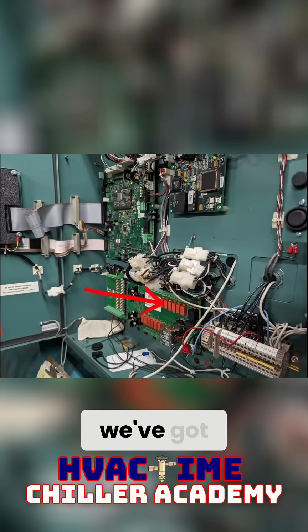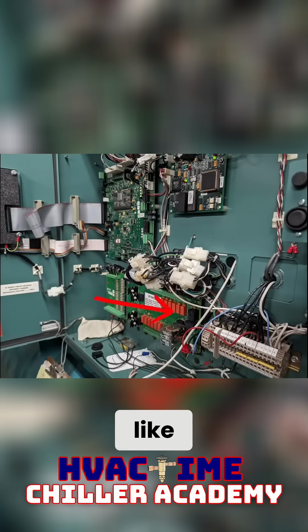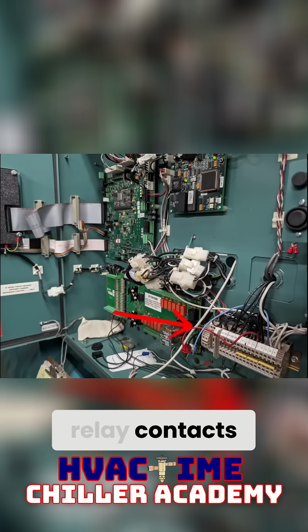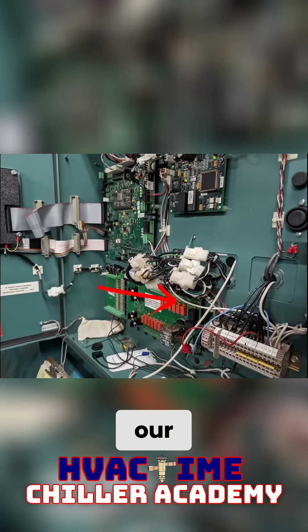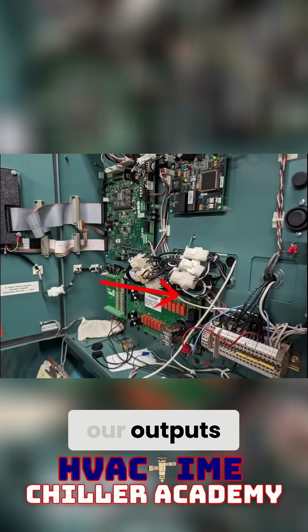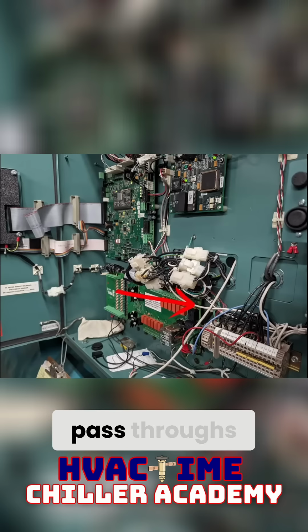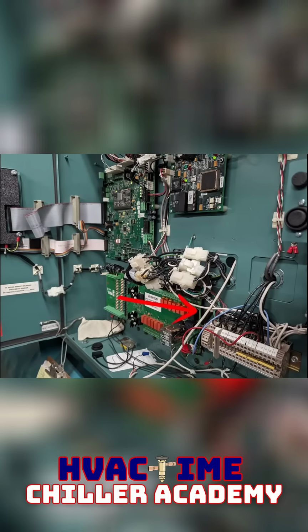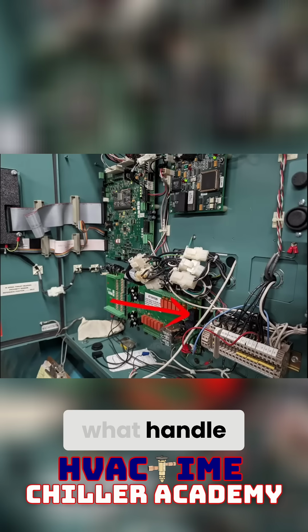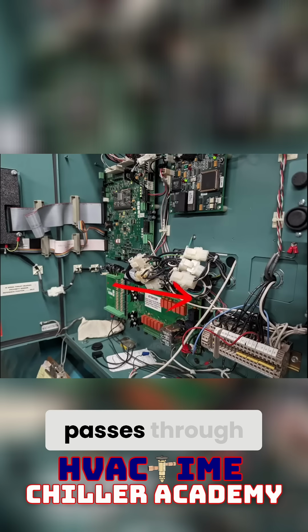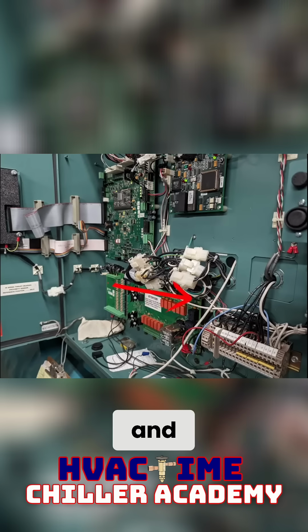And over here we've got actual mechanical relay contacts that are handling our outputs and our heavy load pass-throughs. For an example, these relays here are what handle your oil heater. So your oil heater passes through these relays to get engaged and get powered to maintain your oil temperature in the sump.